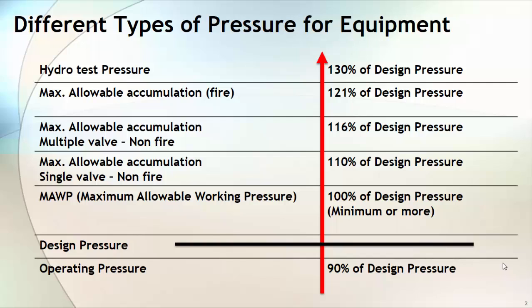You have a temperature and you have a design pressure. This data you will add in the equipment data sheet and hand it over to your equipment manufacturer. The manufacturer, based on the applicable design code — for example ASME, BIS, or IS, whatever it may be — will design the equipment and come up with a thickness number. For example, consider he comes up with 16.5 mm thickness for your design pressure. But this 16.5 mm plate may not be available in the market, so he will go for a higher thickness plate — let's assume 18 mm.